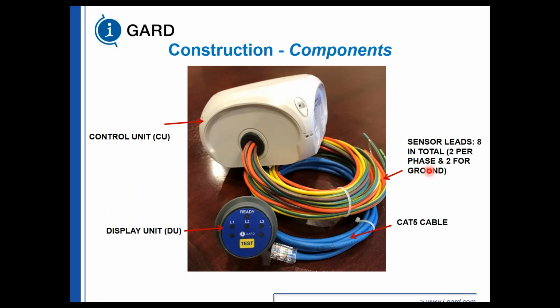The wires are physically connected to the point of contact that you're testing. If one of the wires was to come off, you would fail the continuity test and the test is not valid. And the only thing you see on the front is a display unit. It has a blue ready light, 3 LEDs that are red or green, and 2 amber LEDs and a test push button. This is the only thing you see on the front panel. It could be on a mullion, it could be on the door, and it's connected with a Cat5 cable, so you have low voltage coming to the door. There's not 600 volts or 480 volts coming to the door, there's 5 volts coming to the door.